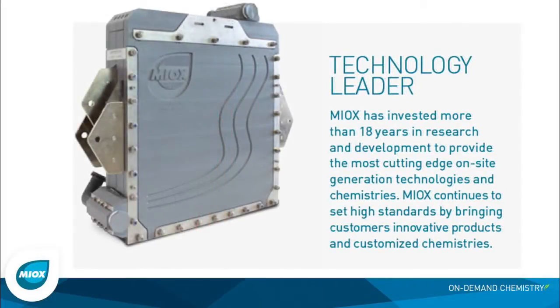That technology then led into larger development of electrolytic cells. At the heart of the technology of that purifier pen was an electrolytic cell technology — a basic technology that you'll see more in the video. It has a cathode and an anode; we run an electric current through a brine stream, and we're able to create a disinfectant chemistry, an oxidant chemistry, out of that electrolytic process. That's a relatively well understood process, and there are actually a number of companies in the industry that do that process and have that technology.